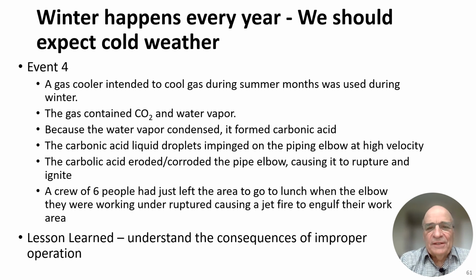Winter happens every year. We should expect cold weather. Event number 4. A gas cooler intended to cool gas during summer months was used during the winter. The gas contained CO2 and water vapor. Because the water vapor condensed, it formed carbonic acid in the presence of CO2. The carbonic acid liquid droplets impinged on the piping elbow at high velocity. The carbonic acid eroded and corroded the pipe elbow, causing it to rupture and ignite.